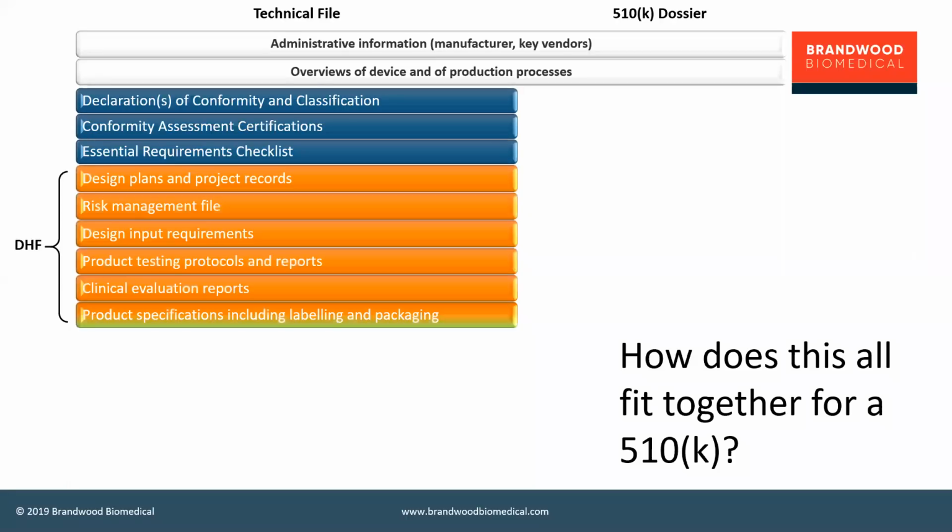Then you have the majority of your DHF, things like your design plan, your risk management file, your inputs, your protocols, your testing, your verification, your clinical evaluation reports, clinical trials, things like that. Part of your DHF, they sit in your technical file, but again, they will be translated into specific 510K deliverables.